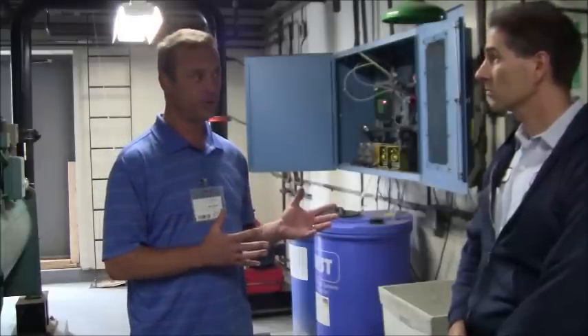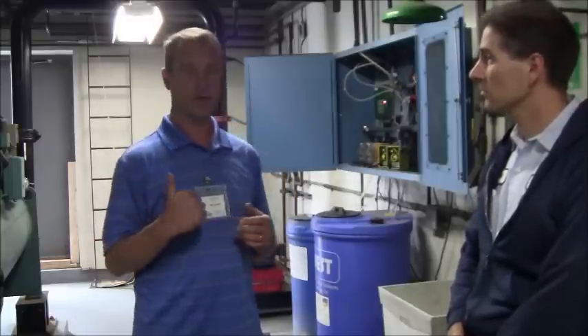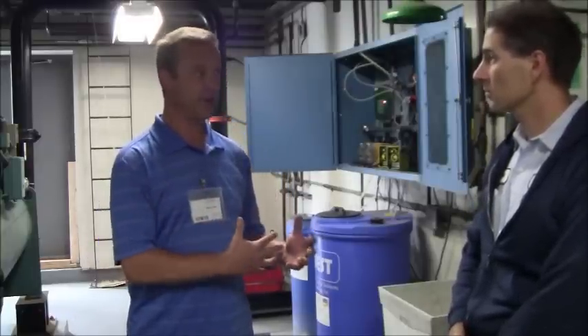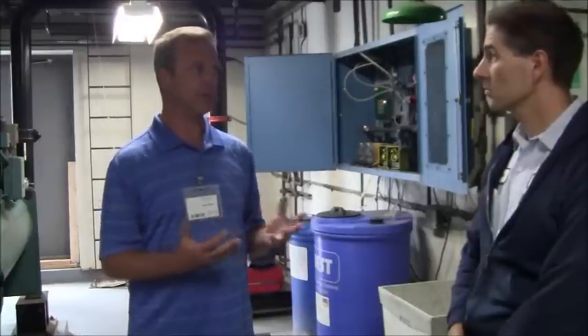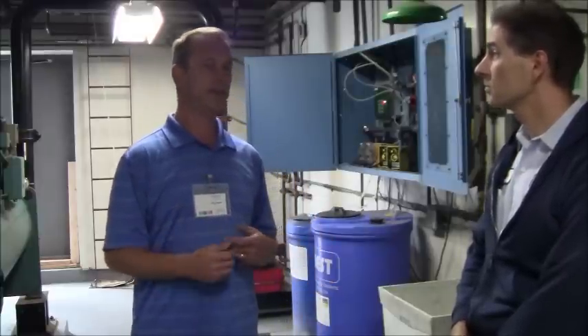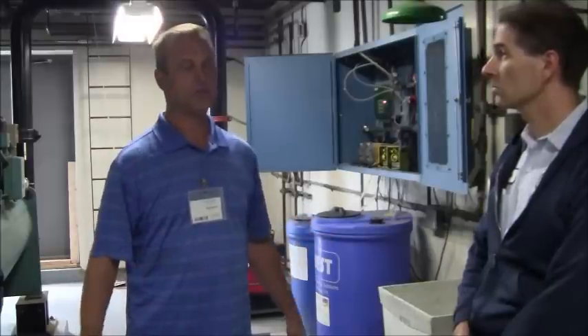You have an open loop system, which would be your cooling towers and your condenser water systems, the condensing side of the chiller. And then your evaporative side is basically a closed loop, like your car radiator, where you would put Prestone or some sort of antifreeze in the radiator to protect it. In this case, we're in Southern California, so we don't use antifreeze like we would in New York or in the northern part of the country. But you still want some type of corrosion inhibitor in there, and in these particular instances, we'll use molybdate or nitrite. We use both at MASTA headquarters currently.